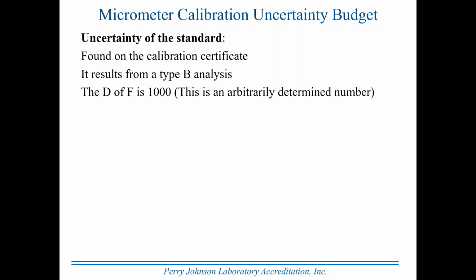So 30 is a significant statistical sample size. Some people use 100, some people use 30. It used to be that when these were done by hand, people would just put an infinity symbol in here as the number. Well, we can't have an equation in Excel where one of the terms is the infinity symbol. So I picked an arbitrary, larger than necessary number of 1,000, where I could have used 100, could have used 200, whatever. I just typically use 1,000 all the time. So when you see a degree of freedom of 1,000 for data arrived at by a type B analysis, know that it is for use in the Welch-Satterthwaite equation, calculating effective degrees of freedom, and you don't have to remember much more about that at this point.